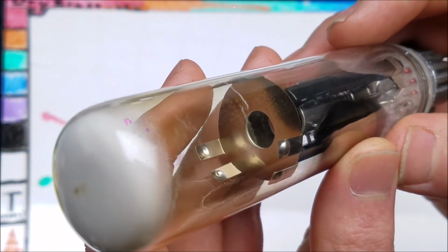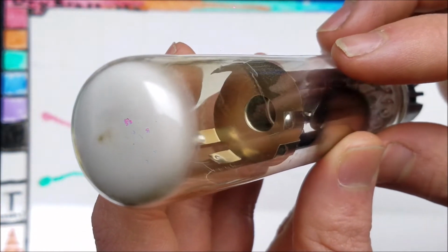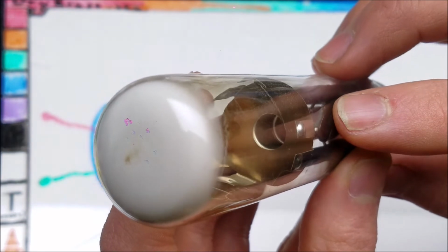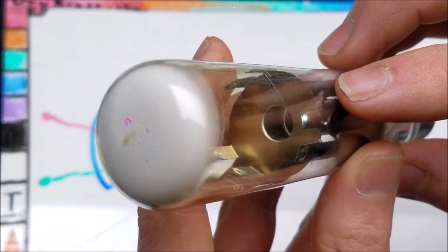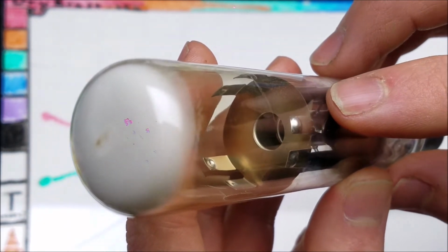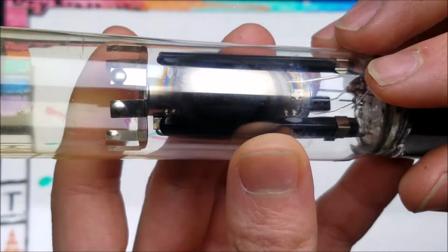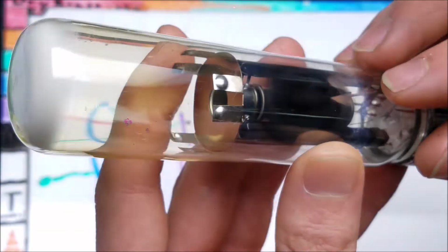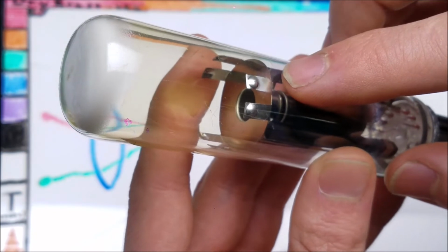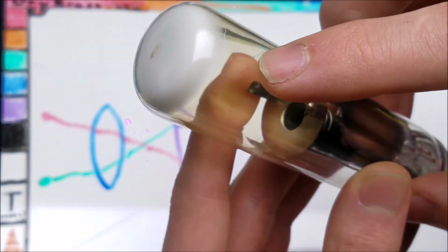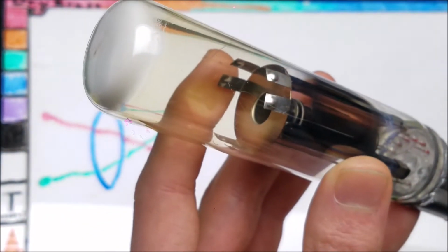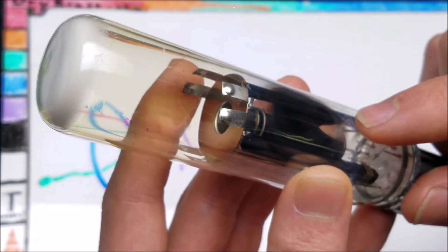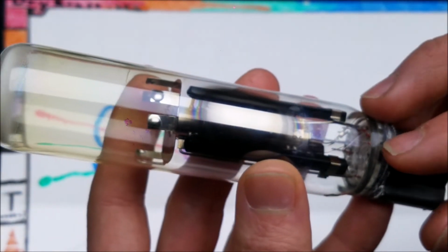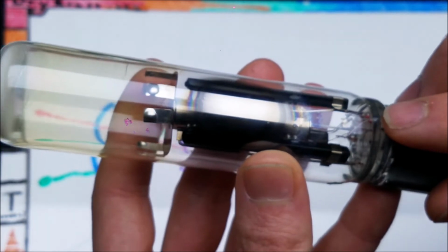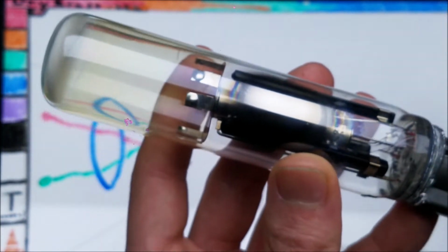So just like in the image intensifier tube, we have a piece of metal here with an aperture, and what that does is when there's a positive high voltage potential, the electrons produced by the electron gun get pulled towards the positive, and then they fly through that hole and hit the phosphors. The only difference between this case and the image intensifier tube is that our source of electrons is not an electron gun, but instead the photocathode.